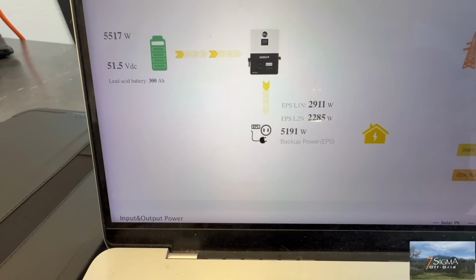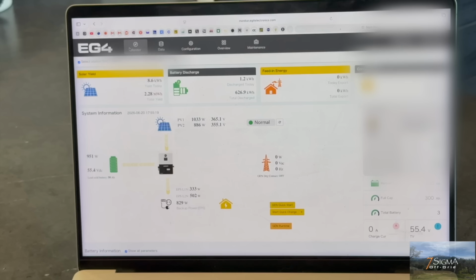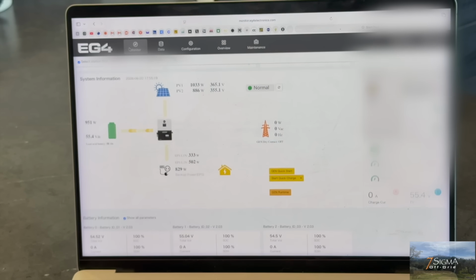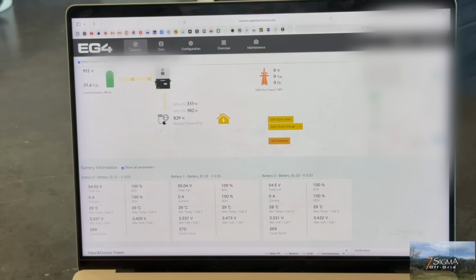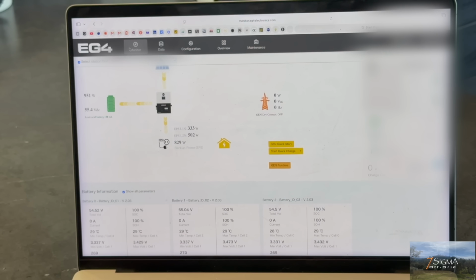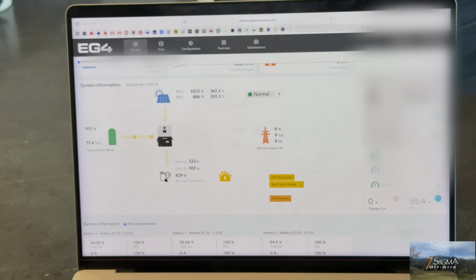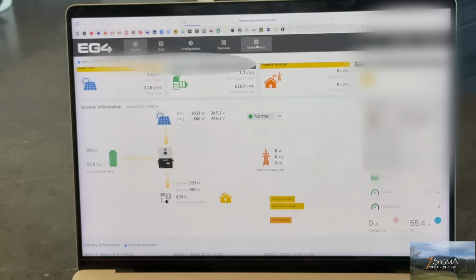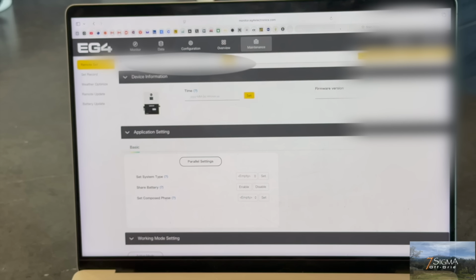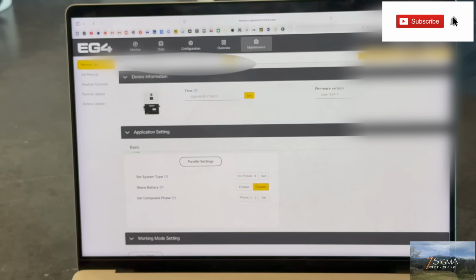Step 3: turn off the PV input and let the bank discharge all the way down through the day. Turning loads on actually speeds this up. Step 4: once fully discharged, turn PV back on and let it charge all the way back up toward true full. Lastly, step 5, after a cycle or two, switch back to EG4 lithium protocol so the inverter and batteries are communicating properly again.